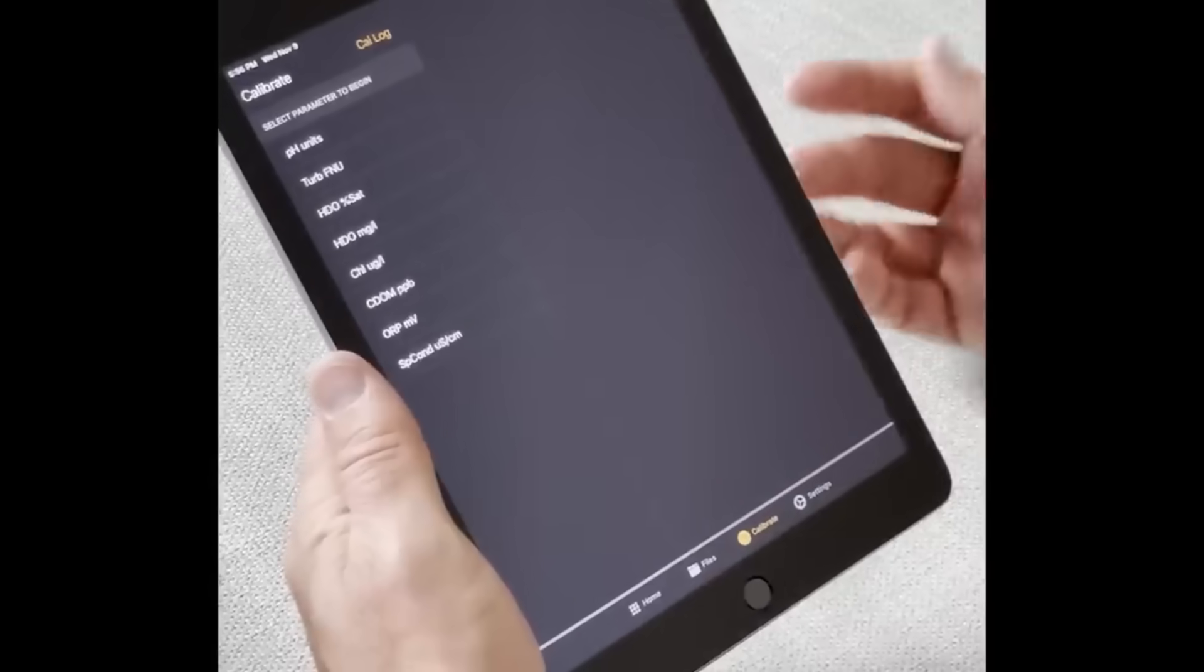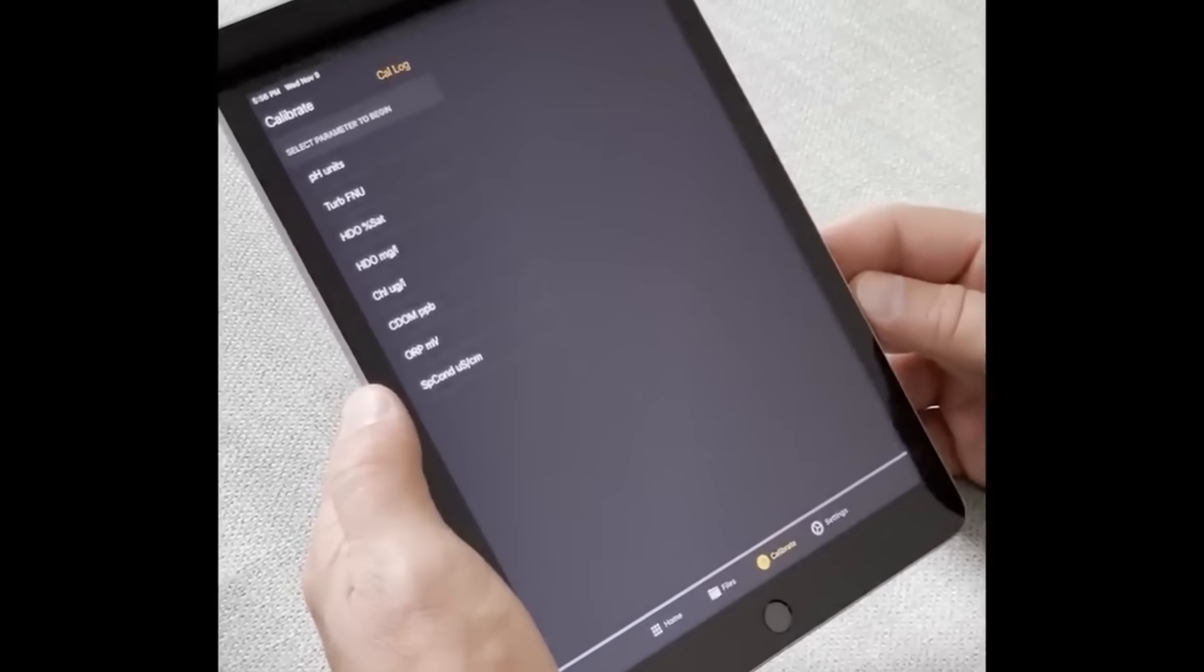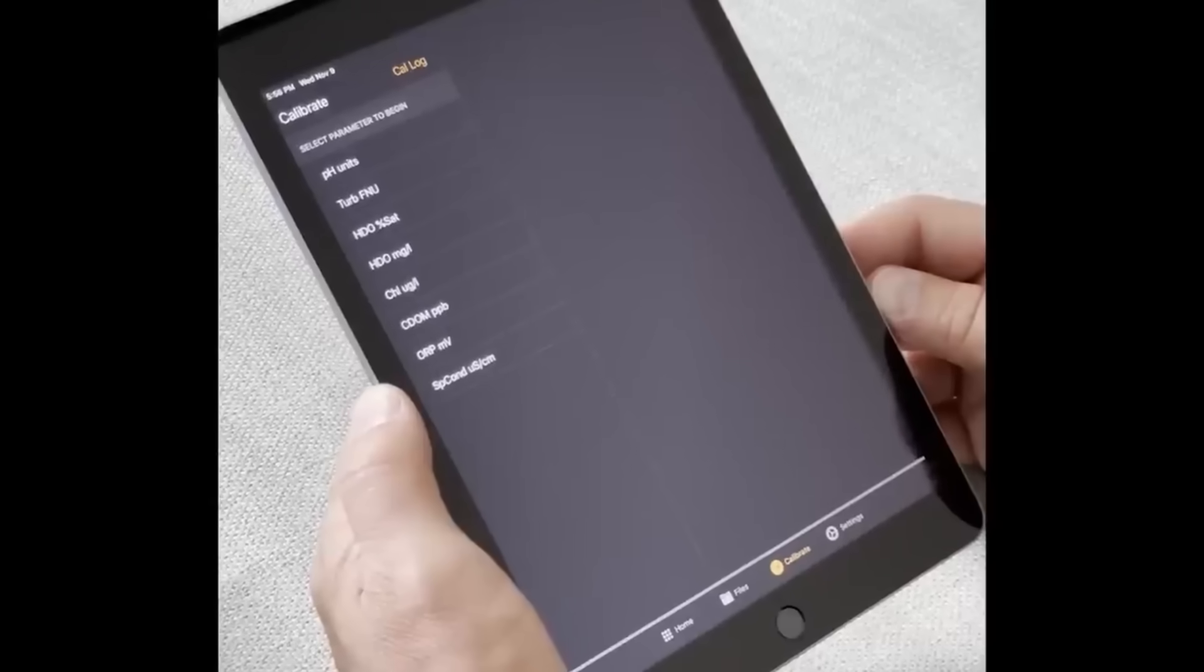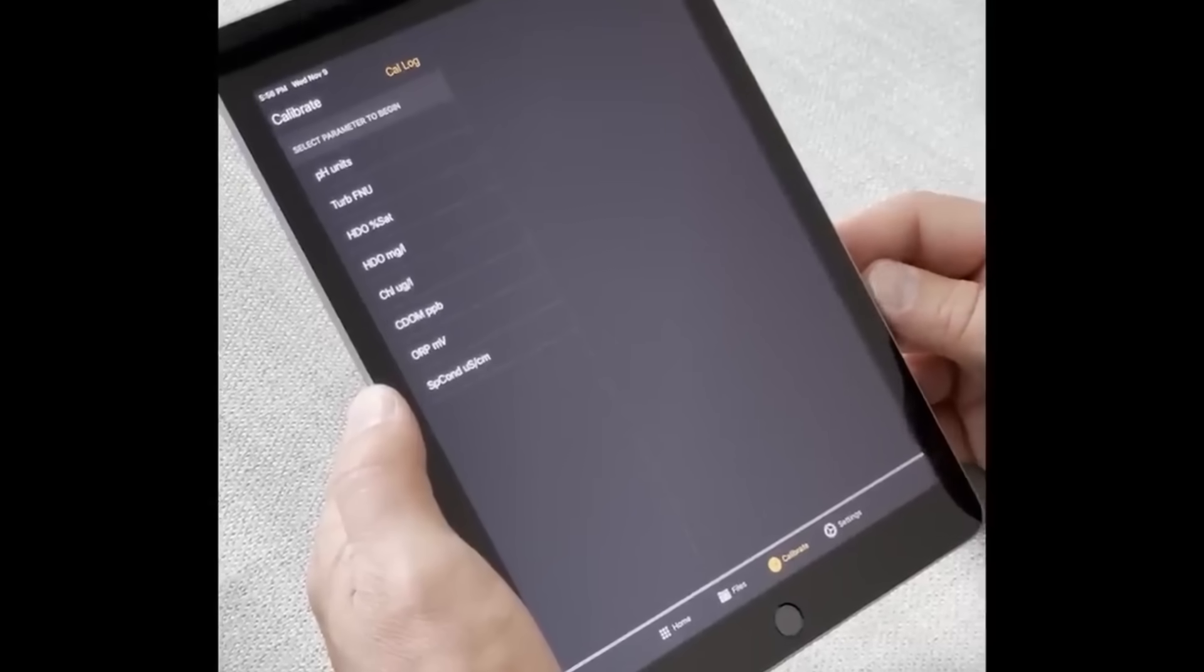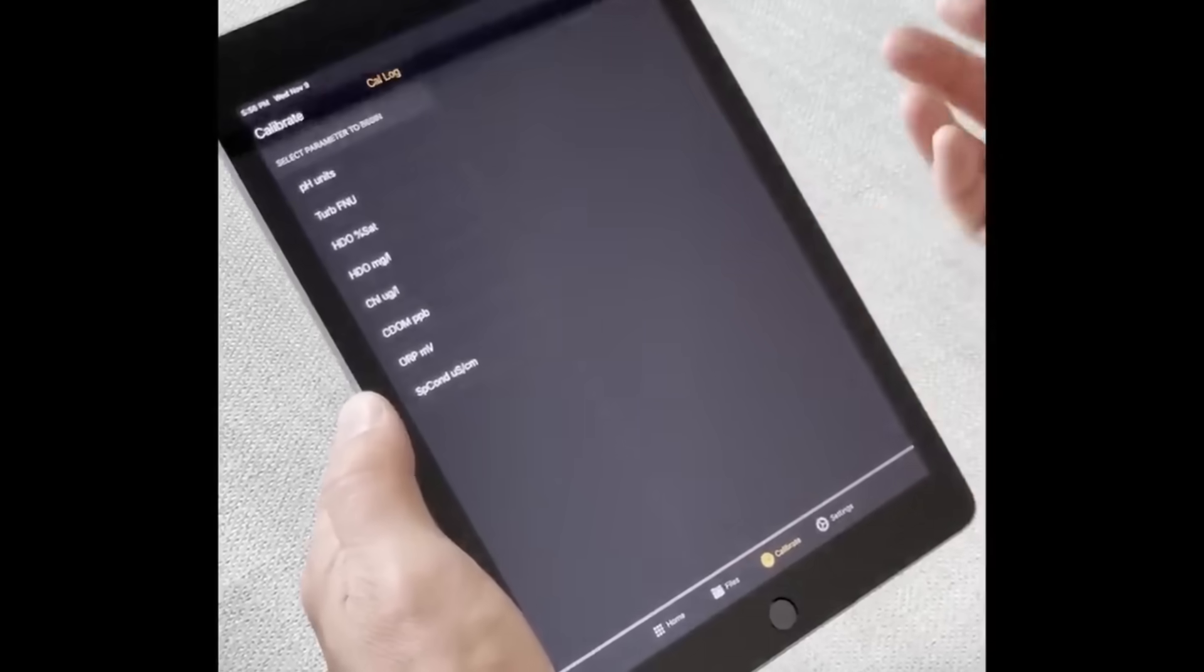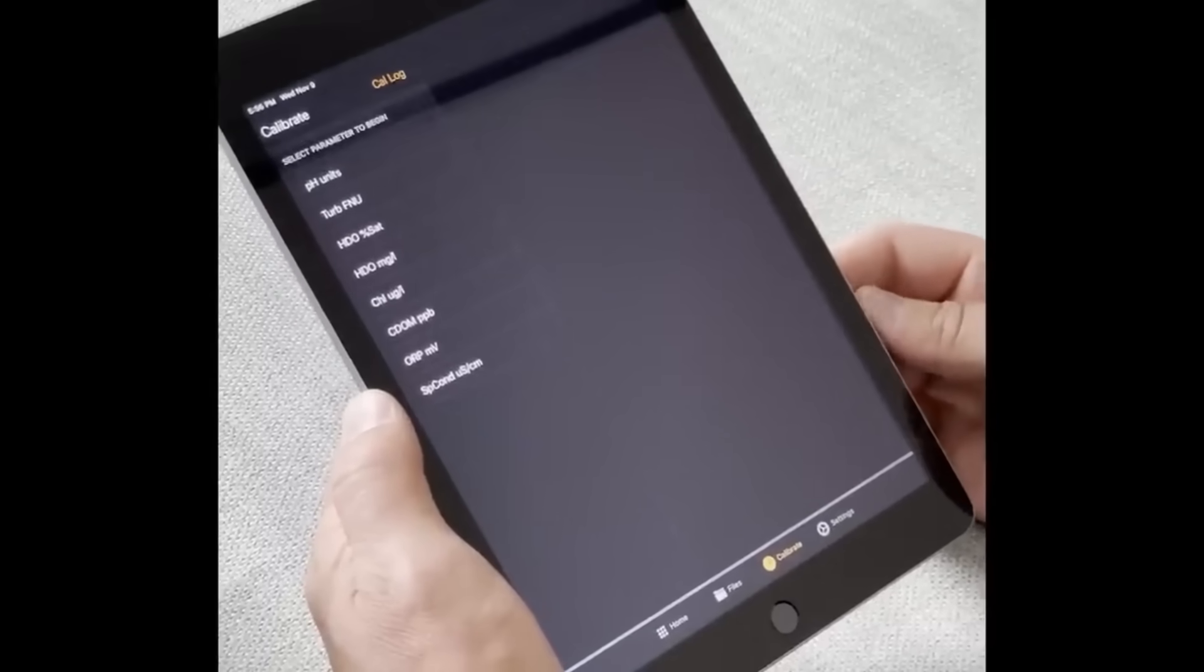Different sensors have different calibration procedures, so you'll be notified as you go through the process and calibration for that sensor if there's a difference. For example, a second point or something else may be related to a fluorometer.